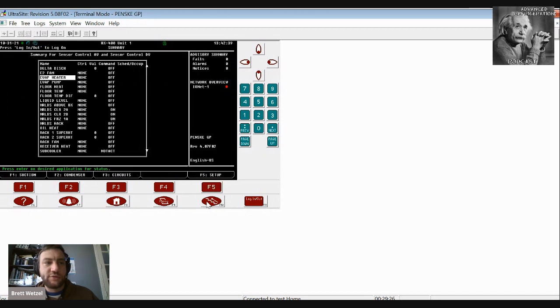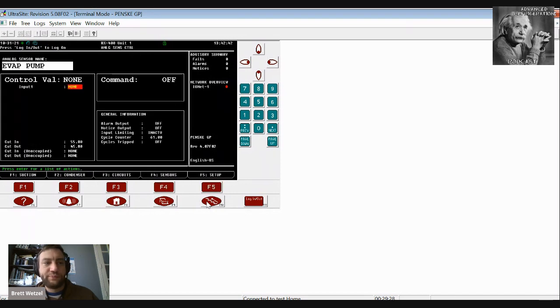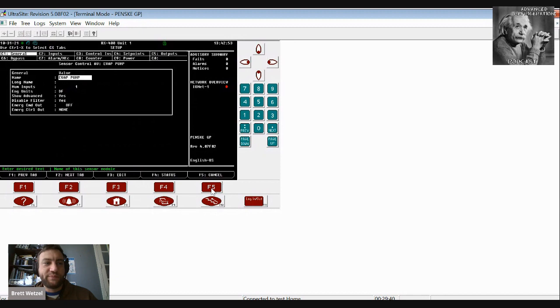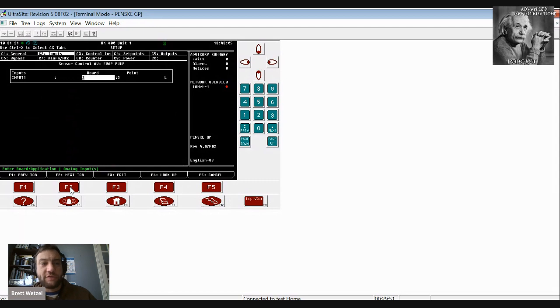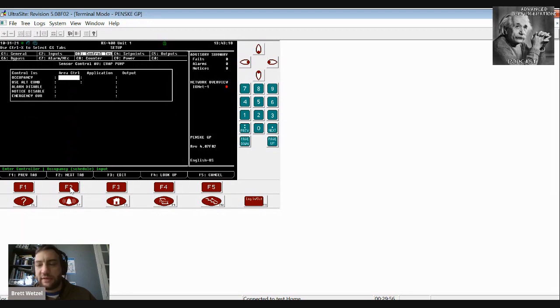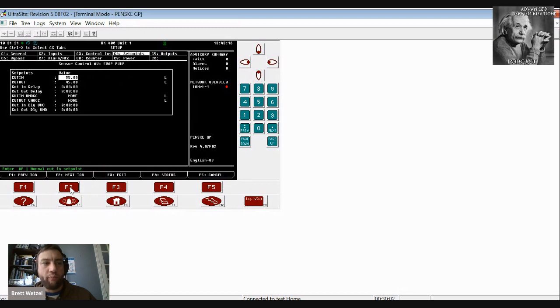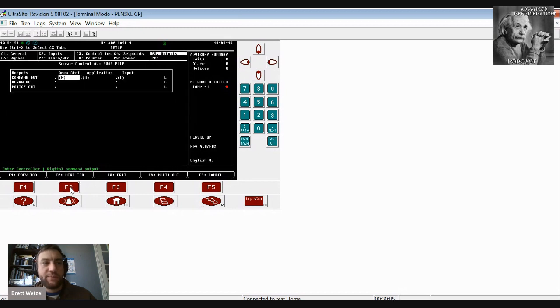I come down to evap pump. So right here, you can see where the cut in, cut out is 45 and 55. And then if you go to setup, notice it's only using one sensor. English units, degrees Fahrenheit. If I hit F2, it'll take me to the next tab. It's using this sensor, which is 2.3. If I'm not mistaken, I believe that's ambient. So basically it's going to cut in and out based off of the ambient. Yeah. No delay on that.